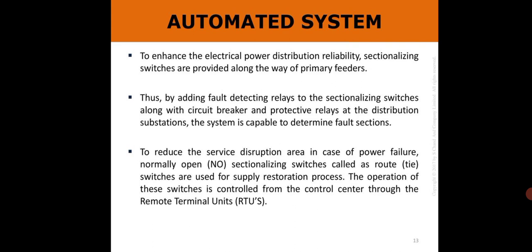So next is the automated system. In this, to enhance the electrical power distribution reliability, sectionalizing switches are provided along the way of primary feeders. Thus, by adding fault detecting relays to the sectionalizing switches along with the circuit breaker and protective relays at the distribution substation, the system is capable of determining fault sections.